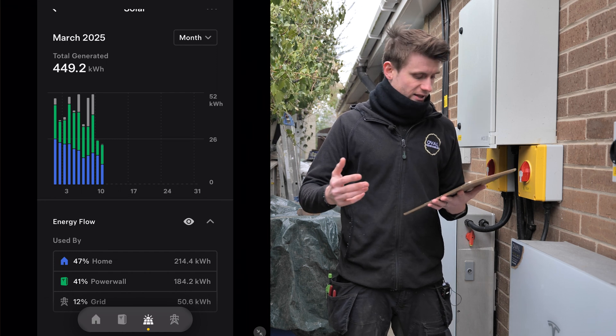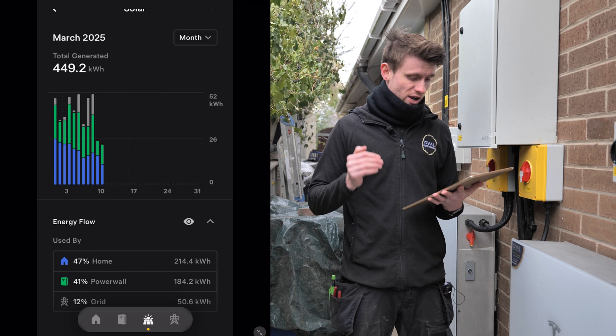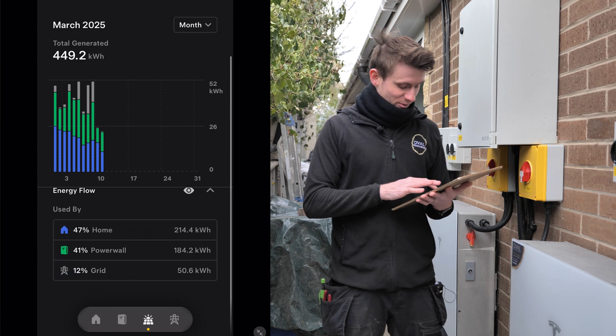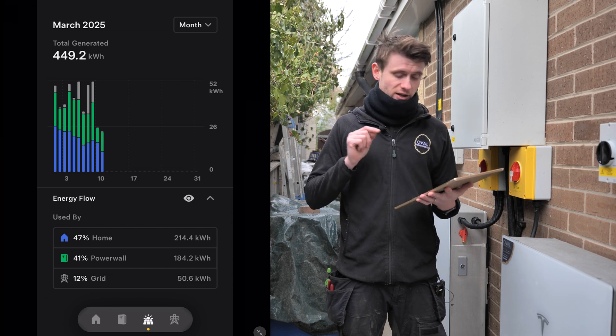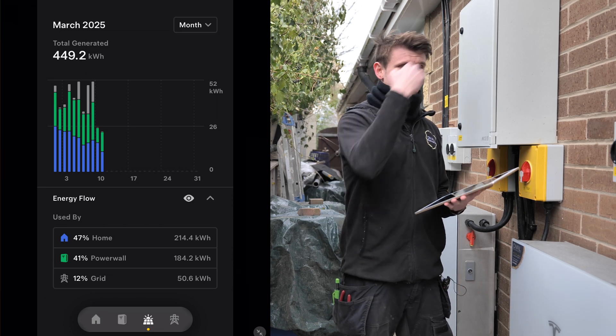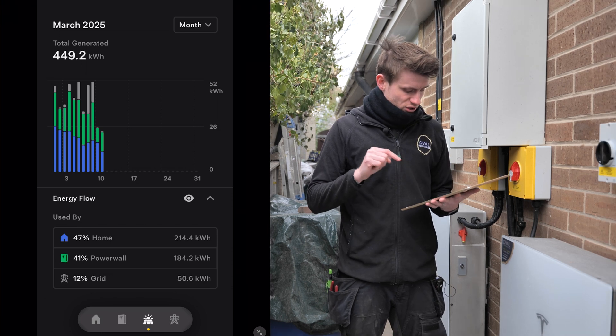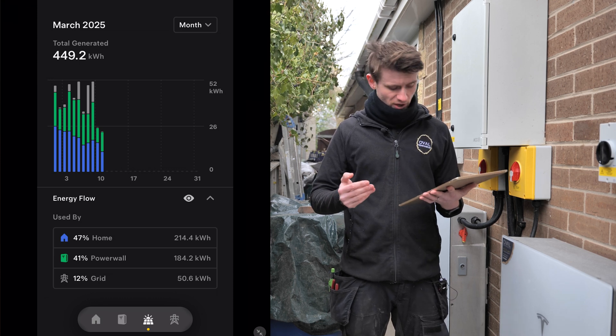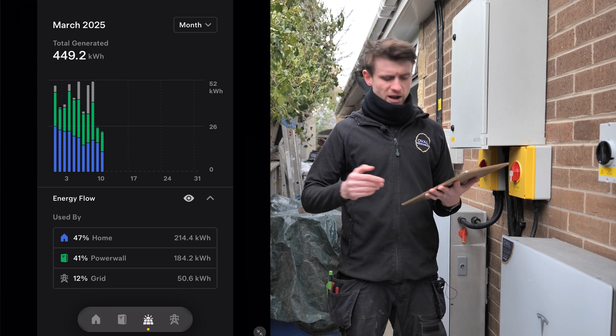Looking at just the solar PV generation for March: 449.2 kilowatt hours generated - nearly 450 kWh - and we're only on the 11th, so there's still the better half of the month to go. Of that solar generation, 47% was used directly by the home (passing through the Tesla inverter without touching the battery modules, which is the most efficient use), 41% went into the Powerwall for storage, and 12% - 50.6 kilowatt hours - was exported back to the grid, for which the customer has been paid via the Smart Export Guarantee.